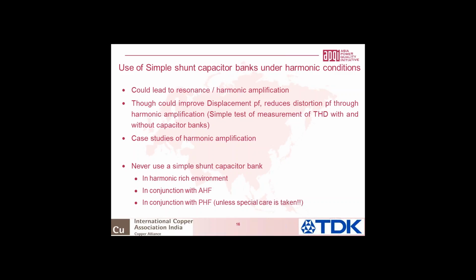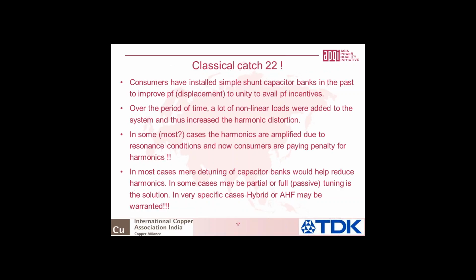Now, this is a classical catch-22 that I was talking about. 20 years back, a lot of utilities started giving incentives for higher power factor, or penalties for low power factor. So a lot of customers installed simple shunt capacitor banks to improve displacement power factor. In those days, the meters were most likely measuring displacement power factor, not the true power factor, and all the incentives and penalties were based on it. So everybody could achieve a unity power factor in terms of displacement power factor.